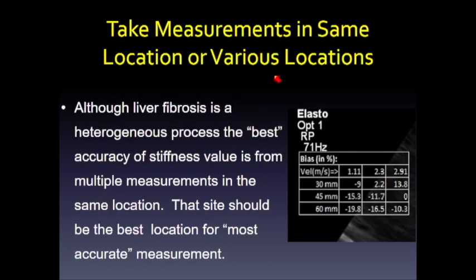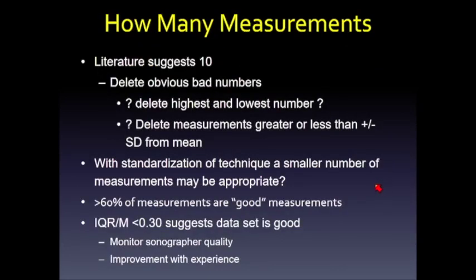We take 10 measurements in the same location rather than various locations, because the attenuation of the ARFI pulse and its bandwidth cause different measurements at different locations. If you want measurements from different locations, you should take 10 measurements at each location. Vendors are developing new quality measures — maps that indicate the best places within an image to take or ignore measurements — which will be very helpful.